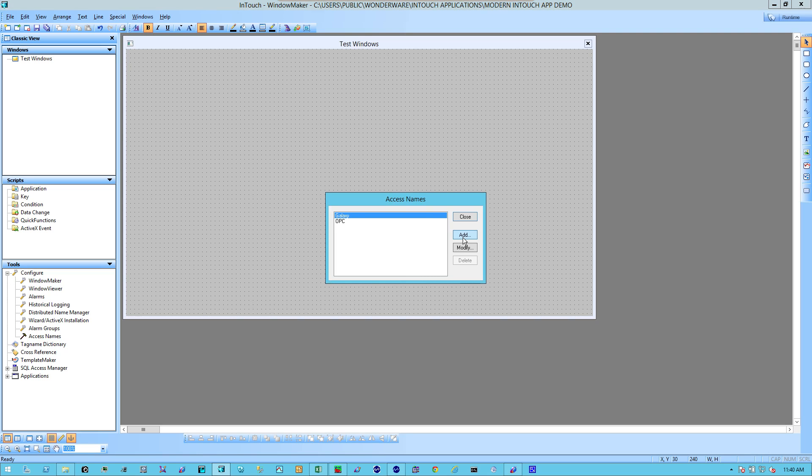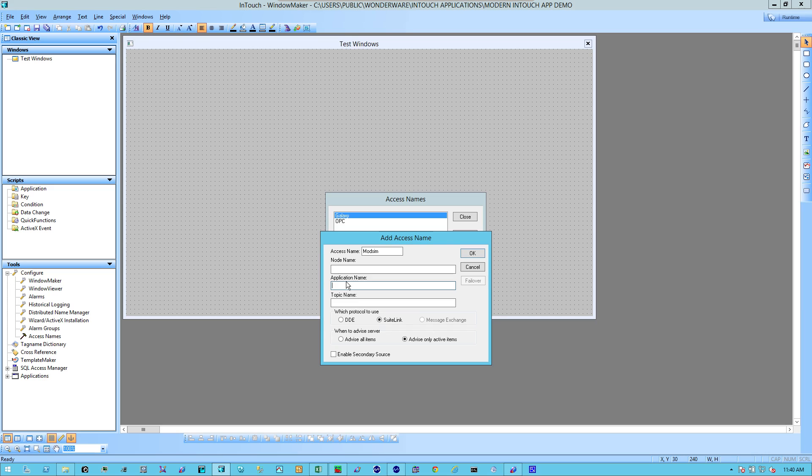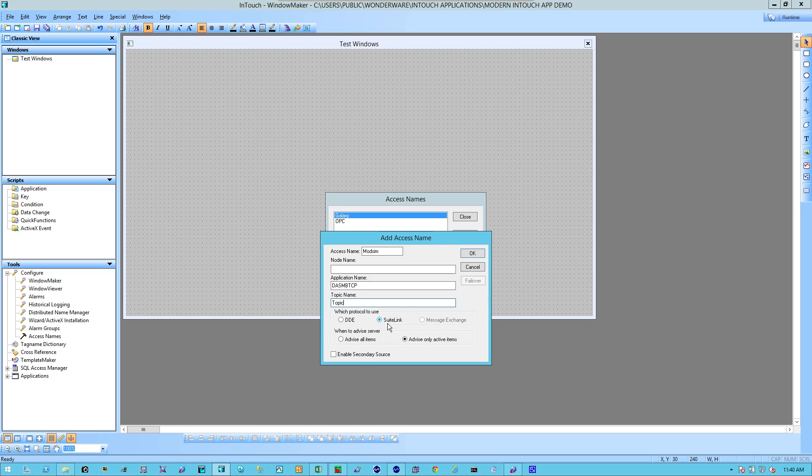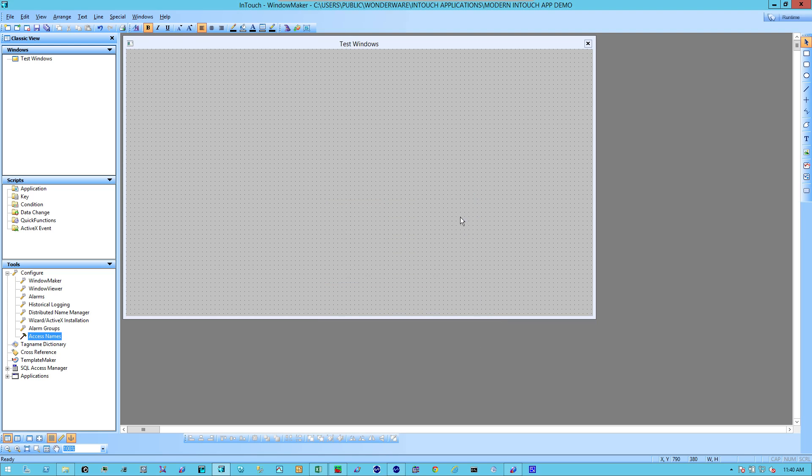I'm going to add an access name. I'm going to call it ModSim. The node name, I'm going to leave blank because the DA server is running locally on this particular computer. I'm going to type in the application name of the DA server, which is DASMBTCP. The topic, I'm just simply going to say Topic, and leave the protocol at the default of SuiteLink. I'm going to click OK and close.